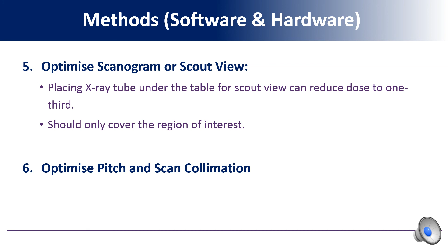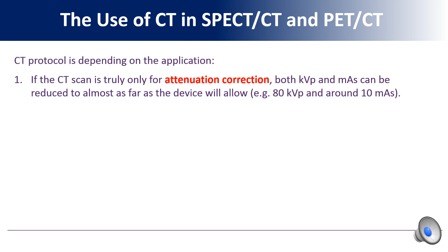And next, I would like to talk about the use of CT in SPECT-CT and PET-CT. When is it necessary to use CT? The CT protocol depends on the application. If the CT scan is truly only for attenuation correction, both kVp and mAs can be reduced to almost as far as the device will allow. For example, 80 kVp and around 10 mAs.